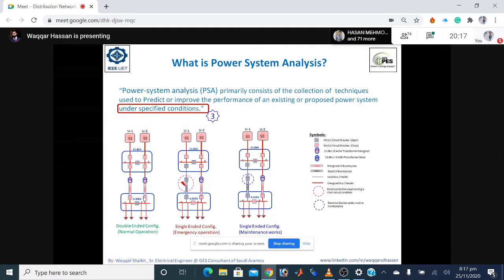But does this mean we are done with our power system study? No, because we have not investigated the other possible operating scenarios of the network. It's very important that whenever we conduct any study - load flow, short circuit, motor starting, any type - we must investigate the network under different possible operating conditions.